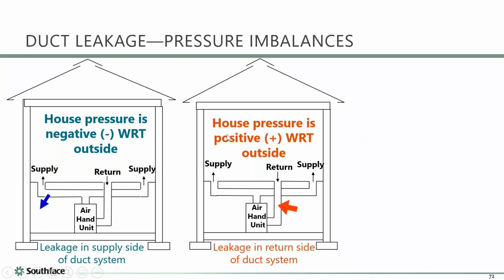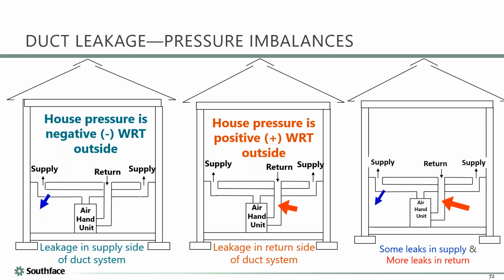Joey, what does it mean if you turn it on and the pressure doesn't change? It must mean that you have a perfectly balanced system, right? Well, there are other possibilities. There is another possibility. That possibility would be you have equal leakage on both sides. So if you're leaking the same amounts on both sides, if it's 0, that's great, but it could be otherwise.